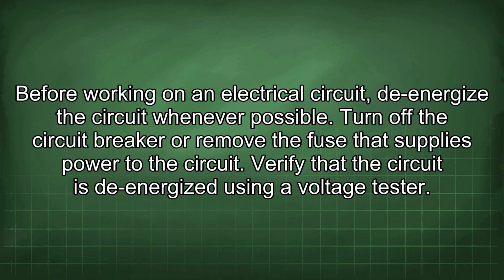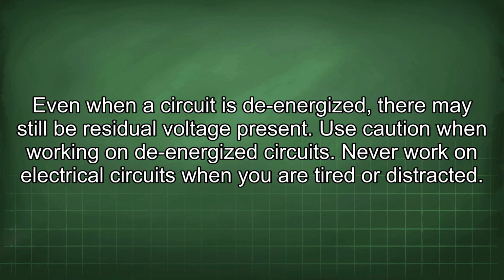Before working on an electrical circuit, de-energize the circuit whenever possible. Turn off the circuit breaker or remove the fuse that supplies power to the circuit. Verify that the circuit is de-energized using a voltage tester. Even when a circuit is de-energized, there may still be residual voltage present. Use caution when working on de-energized circuits.